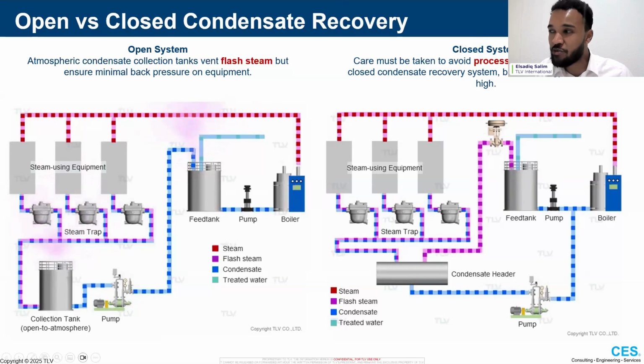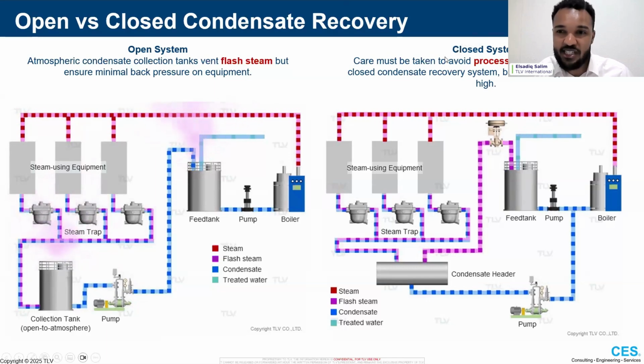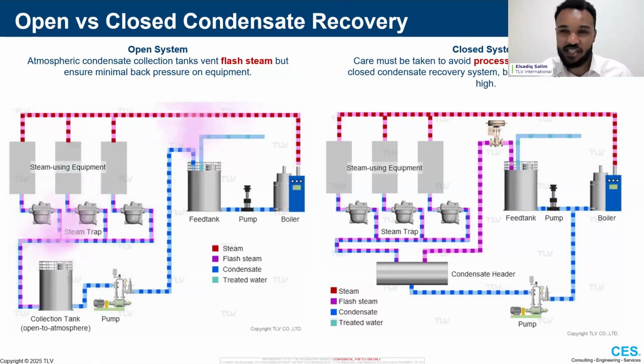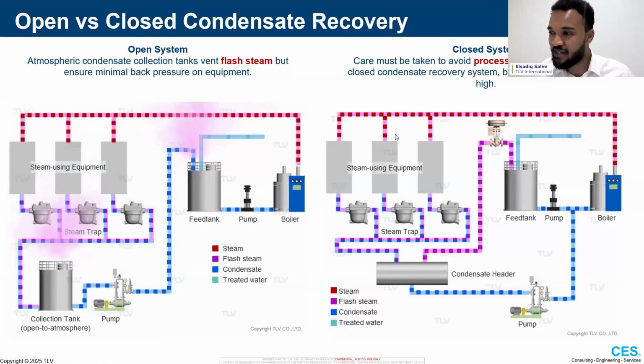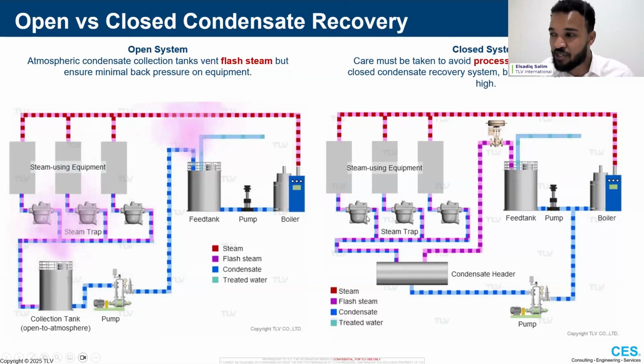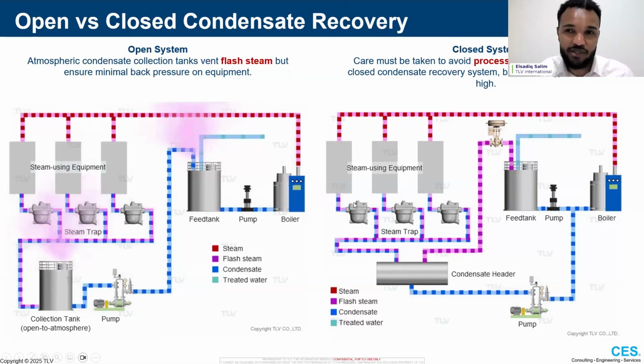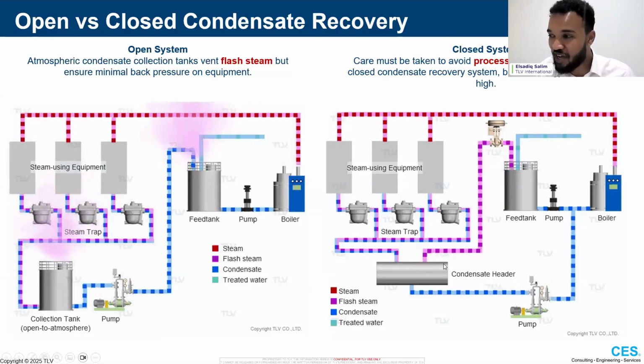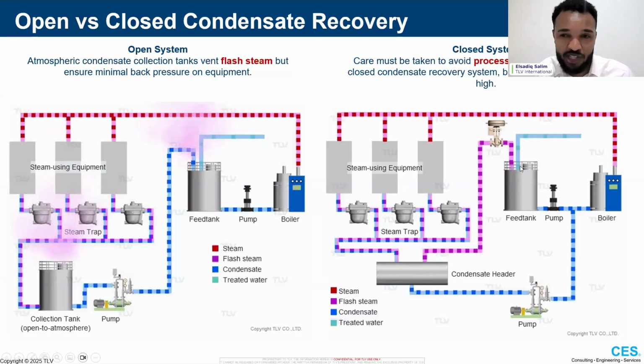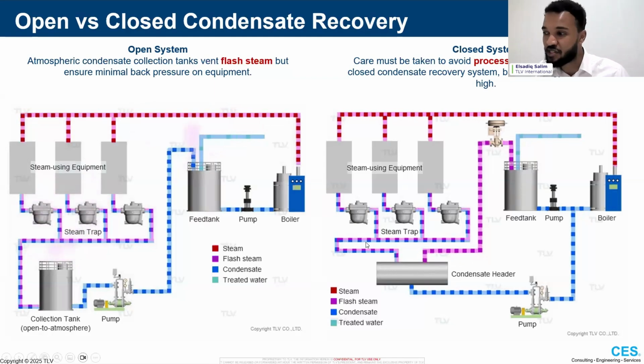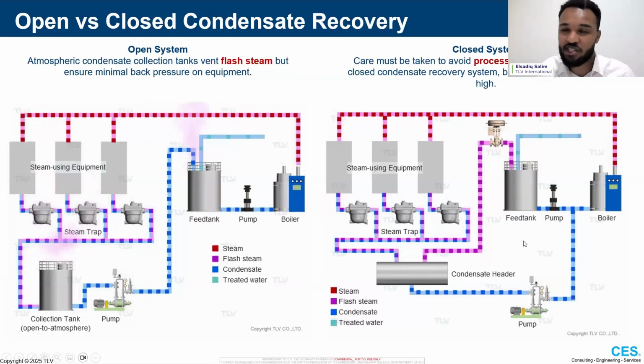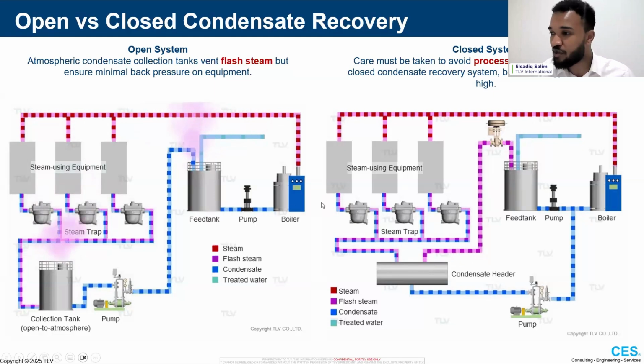The alternative is a closed system, which is a heavily engineered design, but highly efficient. It's certainly possible on a few sites, but it needs a detailed engineering review, because essentially you're putting back pressure on all of your equipment. But the trade-off is you have no vents, except for the pressure control, pressure safety vents in your system. So you can return very high temperature condensate directly to the boiler.